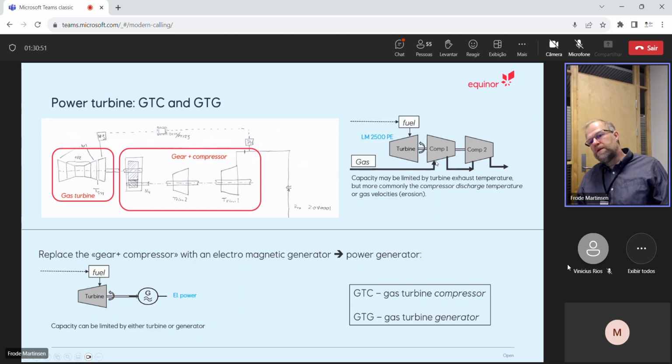I point to the inlet here because on the inlet side, the pressure is the lowest and the gas density is the lowest. The mass flow is the same all over; nothing is lost. Having the same number of molecules here with low density, you'll have higher velocity, more volume flow. So that's why we look at gas velocities on the inlet side.